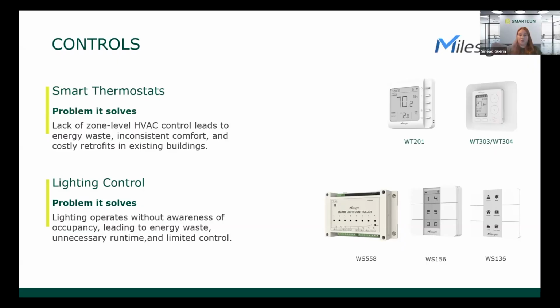They don't have hardwire, they are actually battery, so they can go live if you want to change out your light sensors or institute some control without wiring everything out of the panel. These control from, say, a conference room—you can set certain scenes and it'll connect to that WS558 in the closet, which speaks to that. That's what's actually the controller on the back end. I just like to differentiate there.